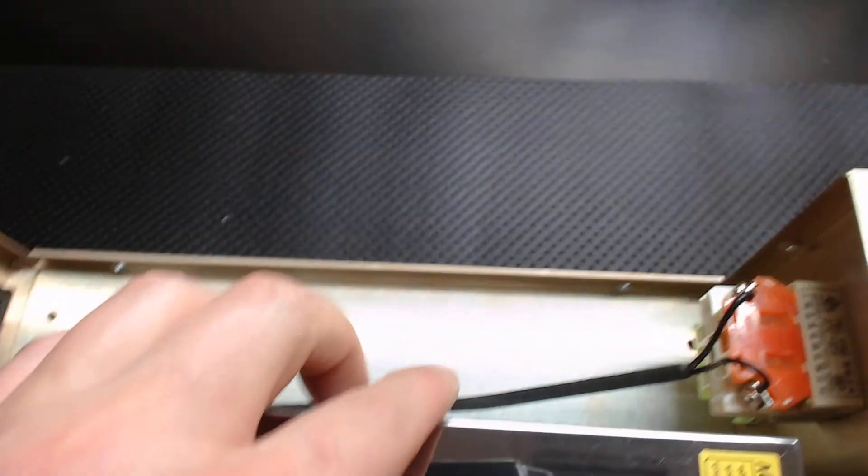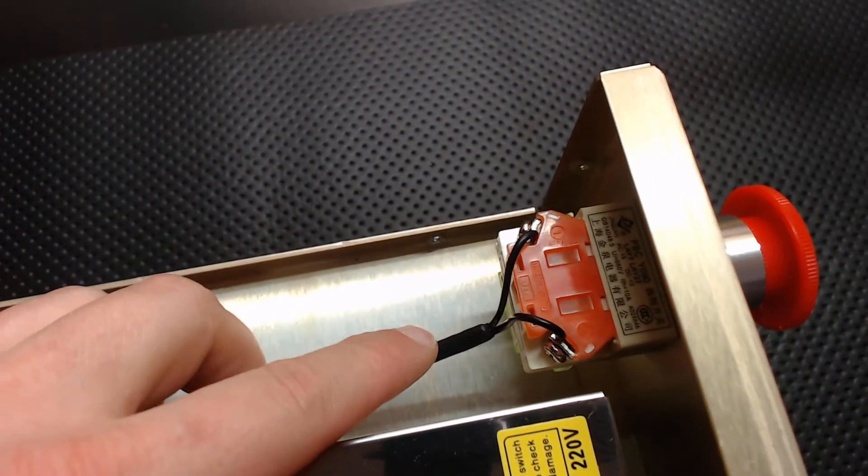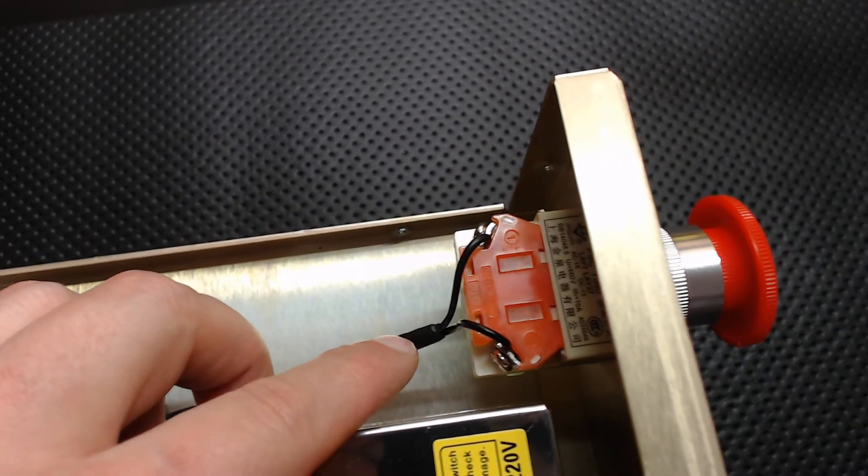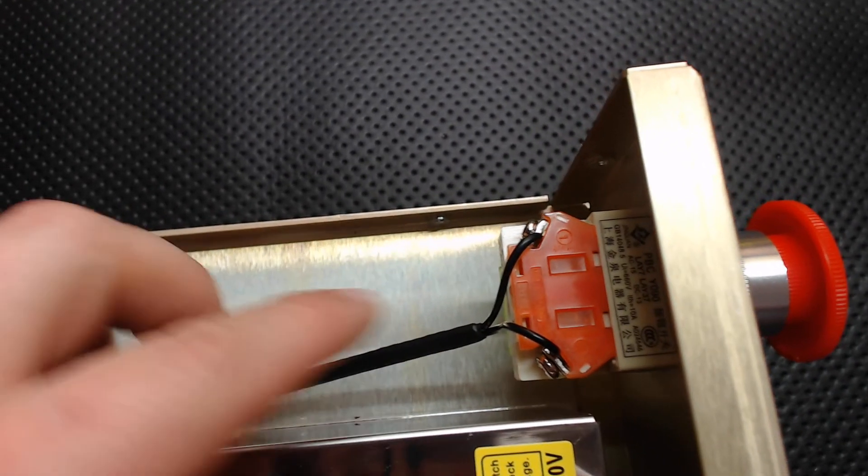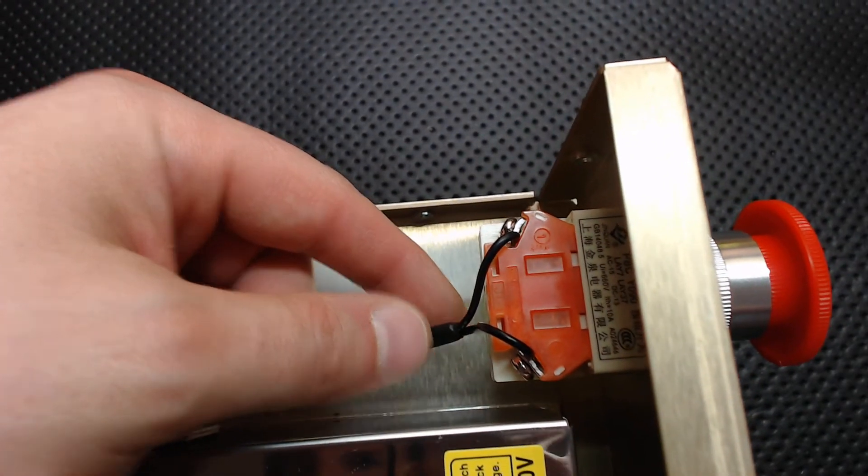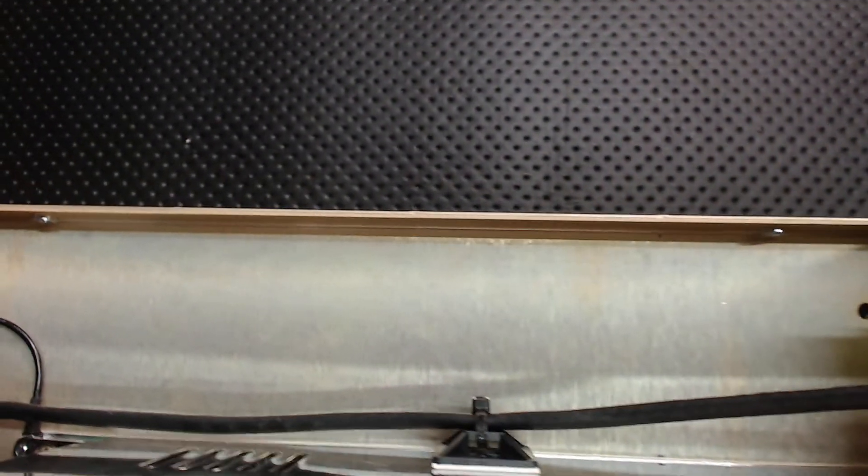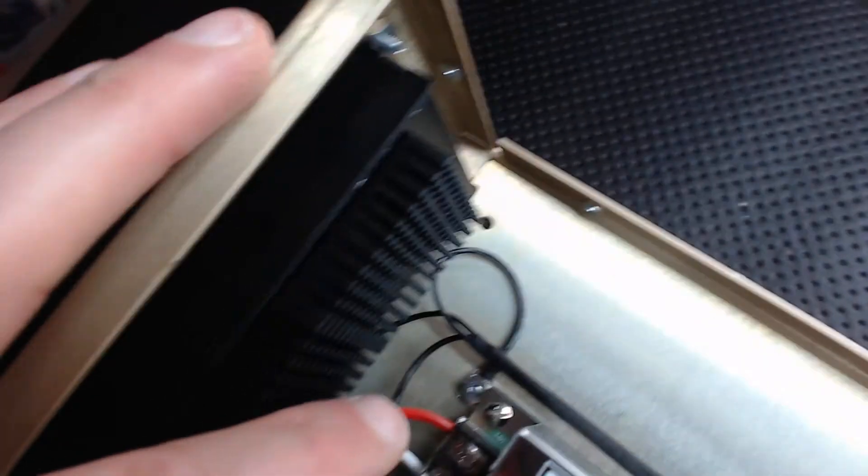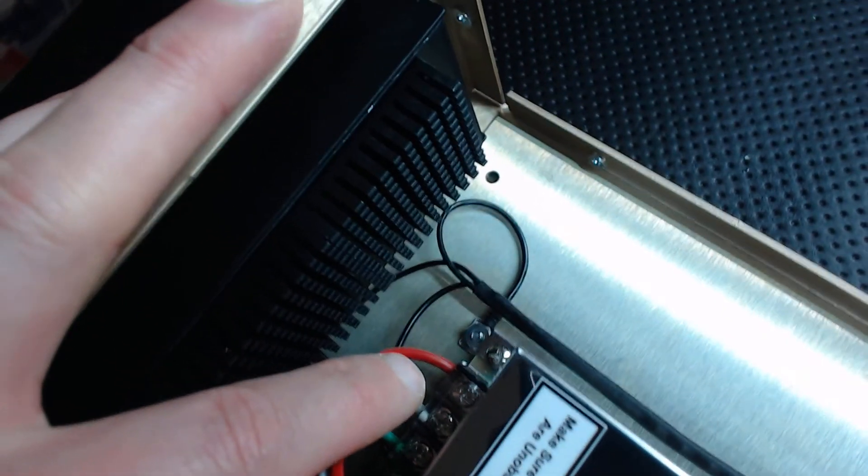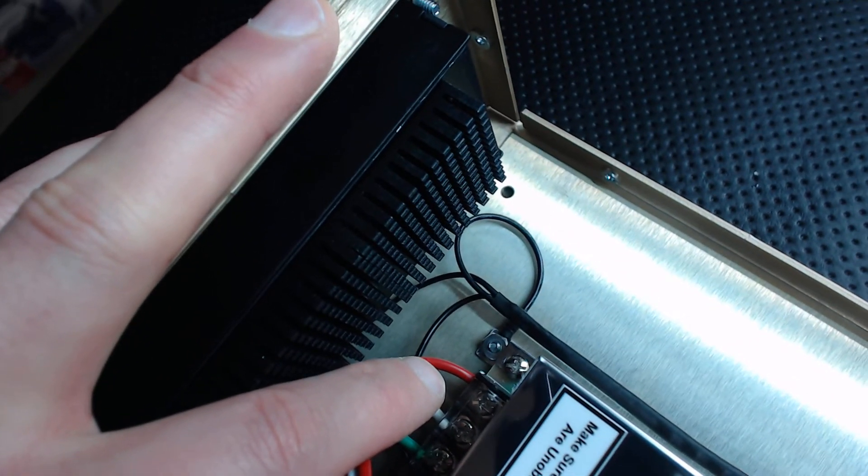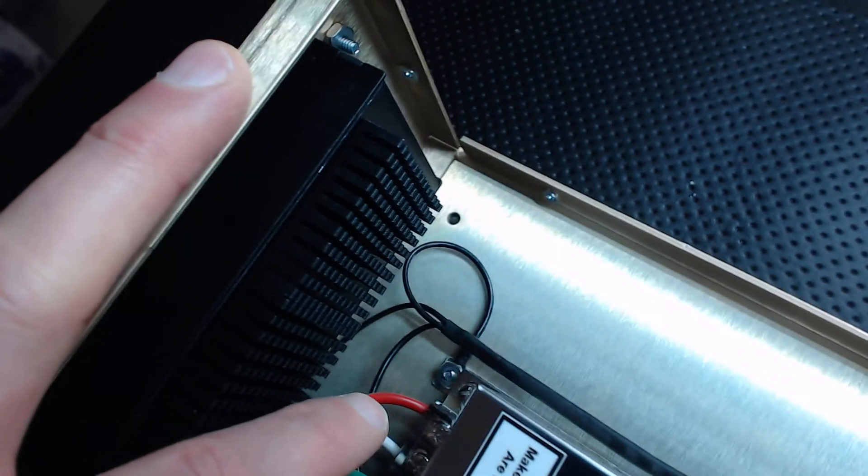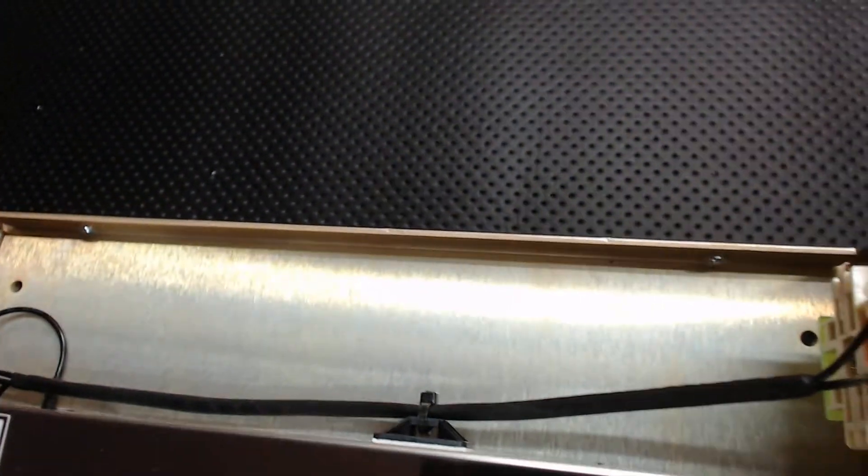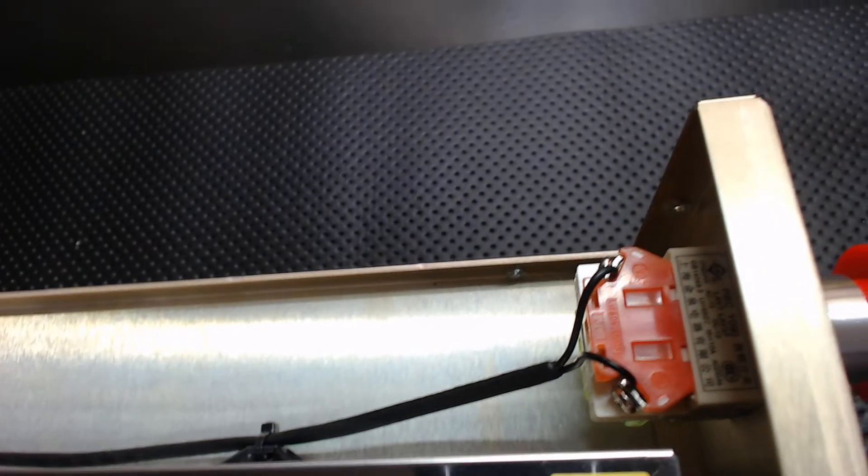But what I want to point your attention to is the e-stop. The main component difference revision that I've done is I've actually went in, used tin braided copper to shield properly the e-stop. You can see she goes all the way back. And then of course, you can see that the drain from the shield is properly grounded as it should be to the base of the chassis. That gives you guys an extra level of protection for the cleanest signal with your e-stop as possible.